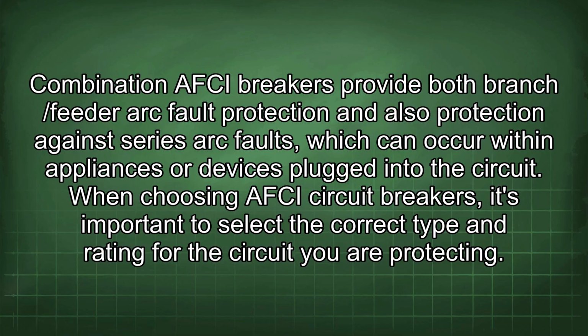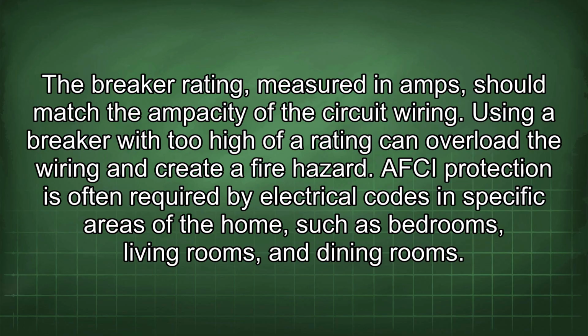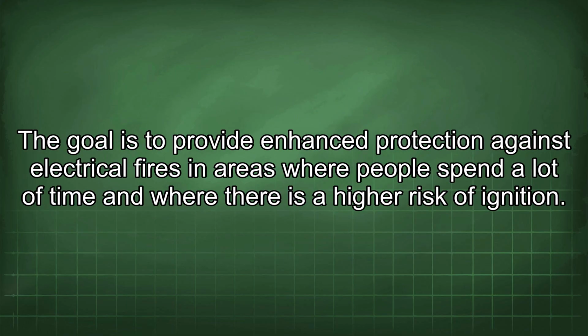When choosing AFCI circuit breakers, it's important to select the correct type and rating for the circuit you are protecting. The breaker rating, measured in amps, should match the ampacity of the circuit wiring. Using a breaker with too high of a rating can overload the wiring and create a fire hazard. AFCI protection is often required by electrical codes in specific areas of the home, such as bedrooms, living rooms, and dining rooms. The goal is to provide enhanced protection against electrical fires in areas where people spend a lot of time and where there is a higher risk of ignition.